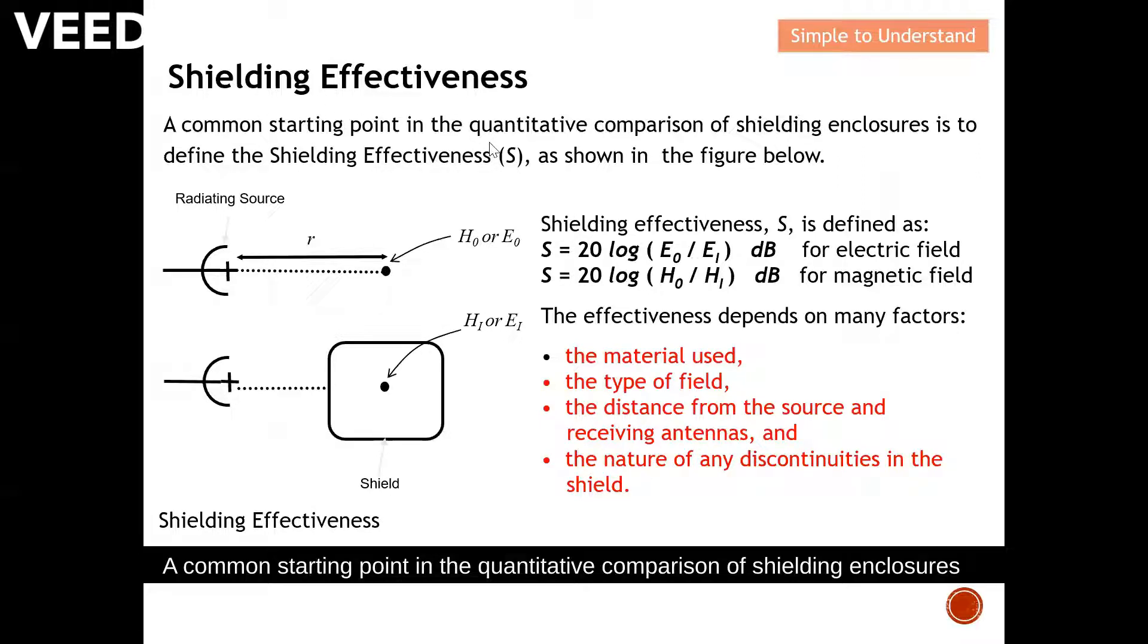How are we going to know the shielding effectiveness? A common starting point in the quantified comparison of shielding enclosures is to define shielding effectiveness as shown in the diagram. This is your noise source. You measure the magnetic field or electric field and denote as H₀ or E₀. Next you put a shield and measure at exactly the same distance. You measure the magnetic field and electric field, denoted as H₁ or E₁.